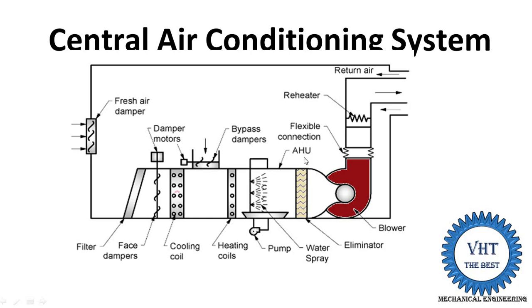When humidification is done, the Eliminator is required. The Eliminator absorbs water particles — during humidification, some water particles travel along with the air. The Eliminator absorbs those water particles and prevents them from being supplied into the rooms along with the air. Sometimes the return air from the rooms is mixed with the fresh air to reduce the temperature of the supplied air, helping to maintain the room temperature.